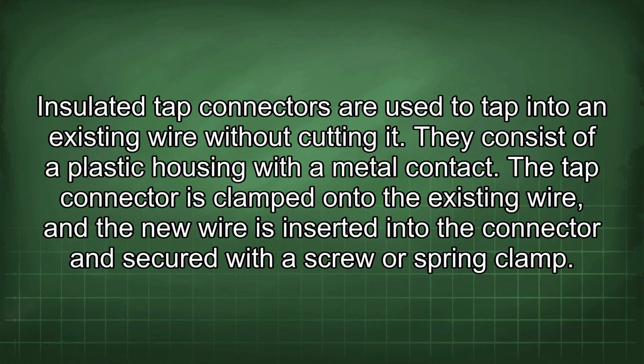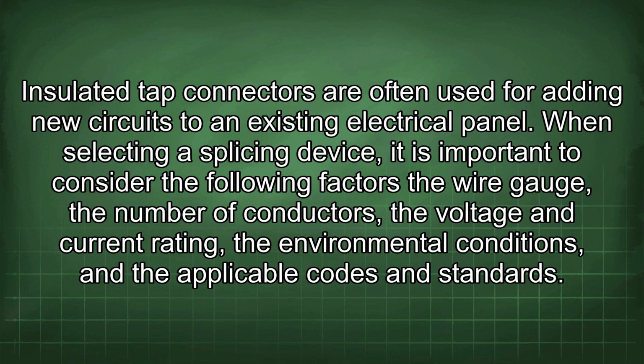required. Insulated tap connectors are used to tap into an existing wire without cutting it. They consist of a plastic housing with a metal contact. The tap connector is clamped onto the existing wire, and the new wire is inserted into the connector and secured with a screw or spring clamp. Insulated tap connectors are often used for adding new circuits to an existing electrical panel.